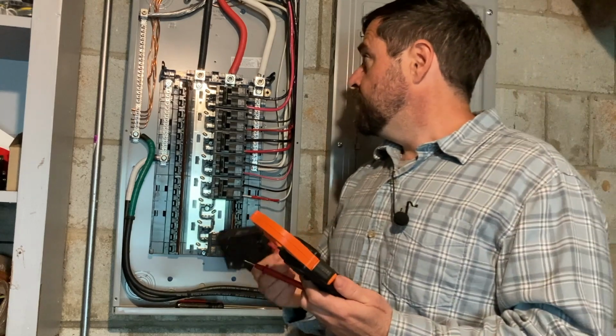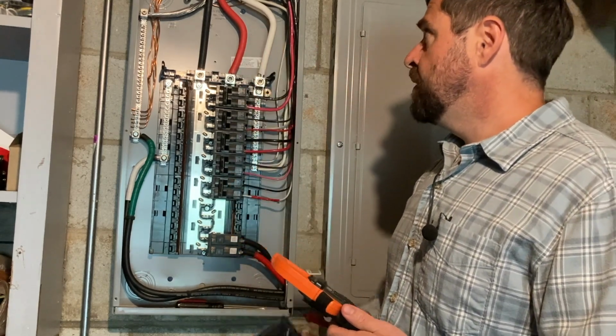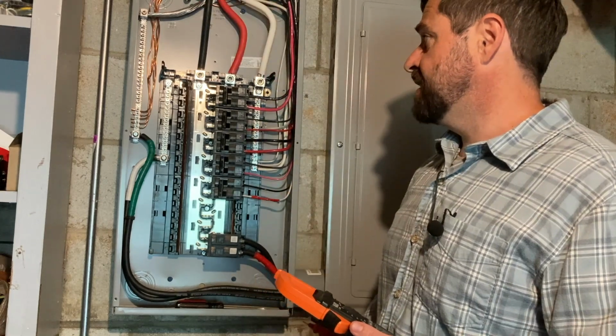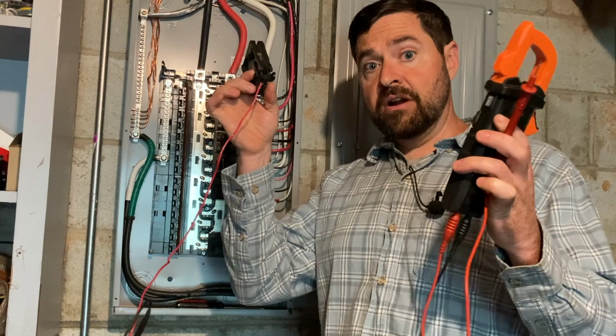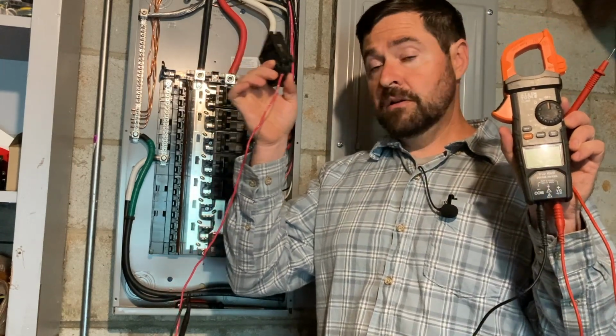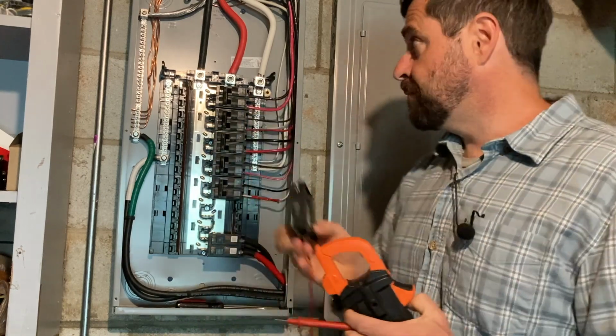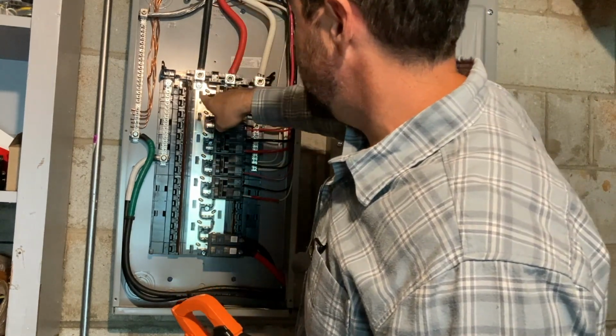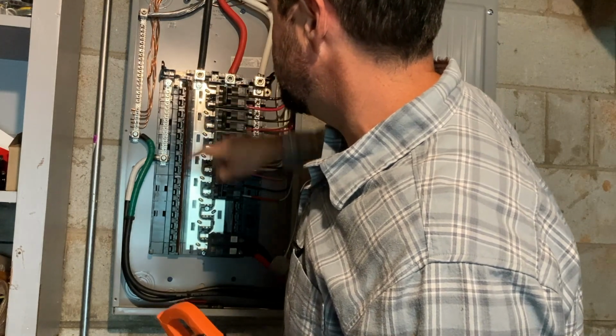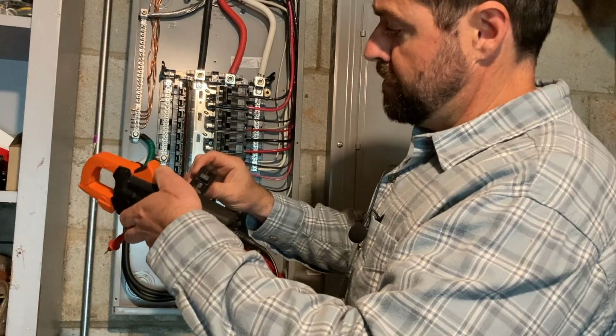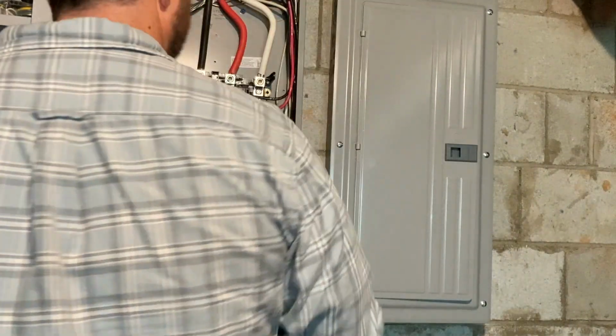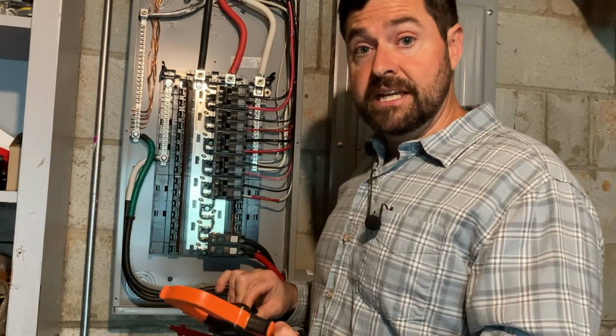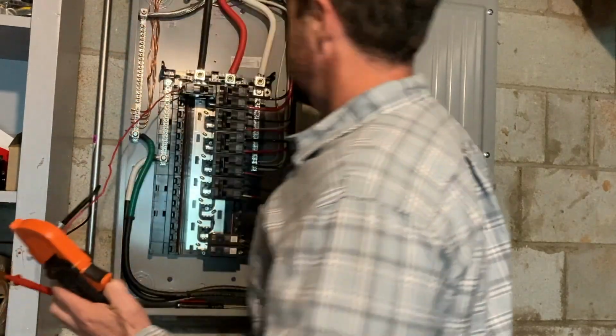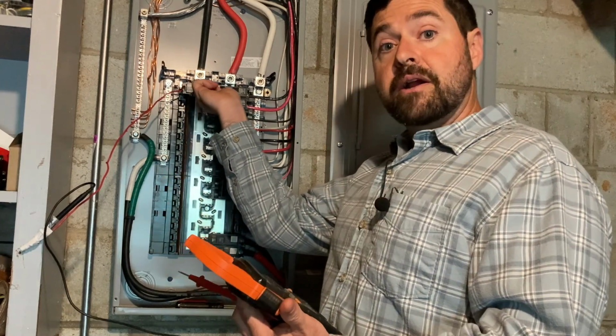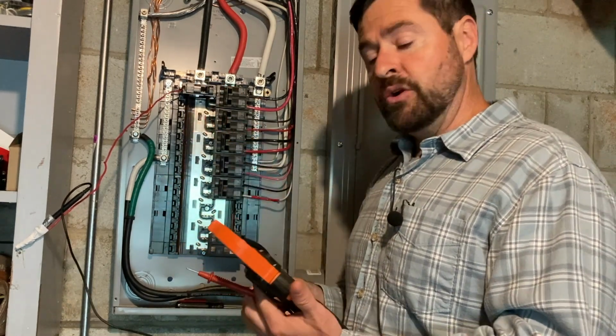What you can do, let's pretend this is the main service panel, and we've got our L1 CT on this black conductor. Well, we could take that wire end of the voltmeter extension, land it in a single pole breaker. We take that breaker, we follow that L1 conductor down, we find the first open stab on that L1 bus bar, and we turn this breaker to the off position. Again, you would want to do this while the panel is de-energized. You would snap the breaker into the L1 lug. You would turn the breaker on. You would energize the panel.